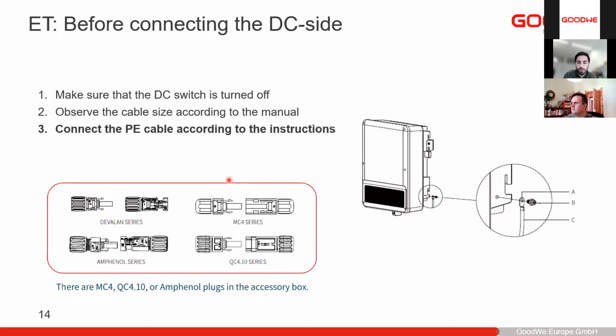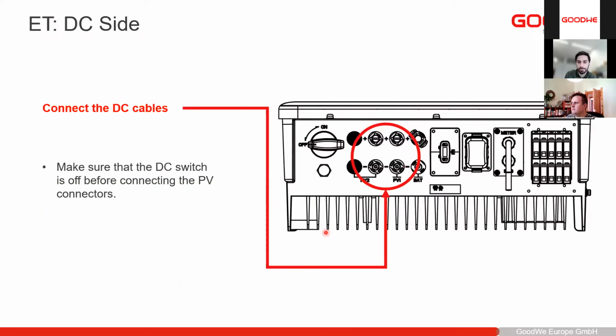Before you connect the DC side, make sure that the DC switch is turned off, and also make sure that you have the proper DC cables. In the package, you will also have the DC terminals, and then you just need to crimp them on and connect. As I explained before, here on the bottom side, these are blacked out, which means that you only have two different DC inputs for any European models.